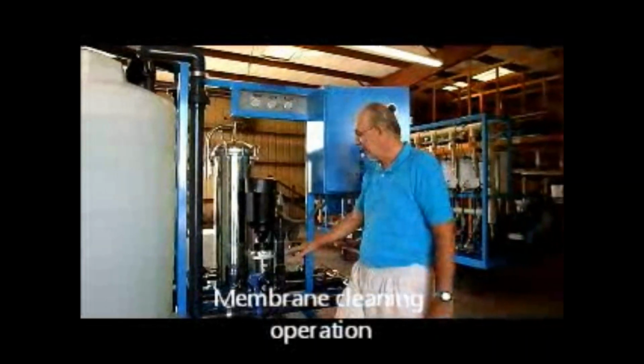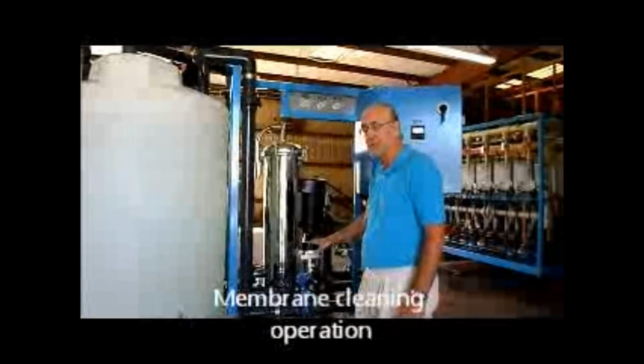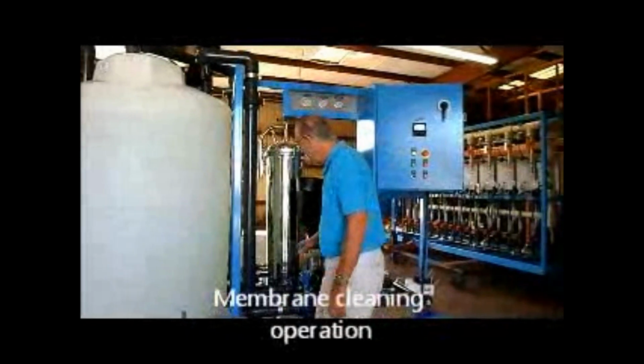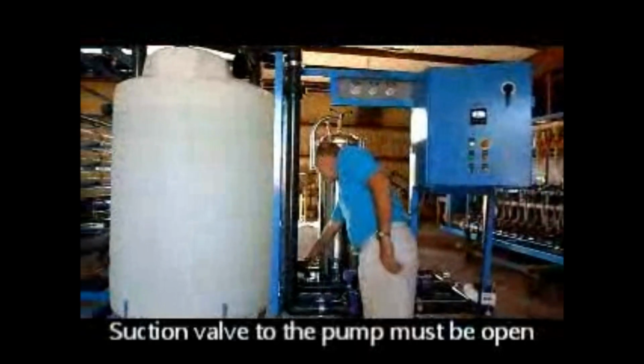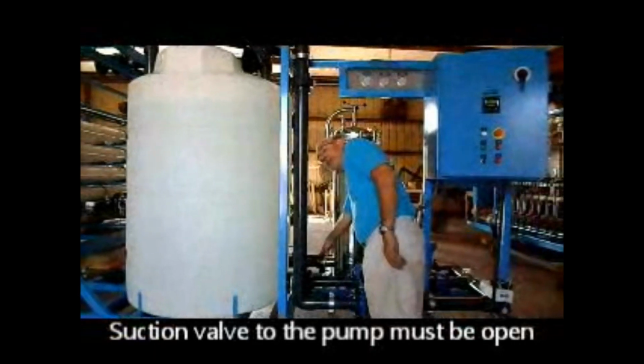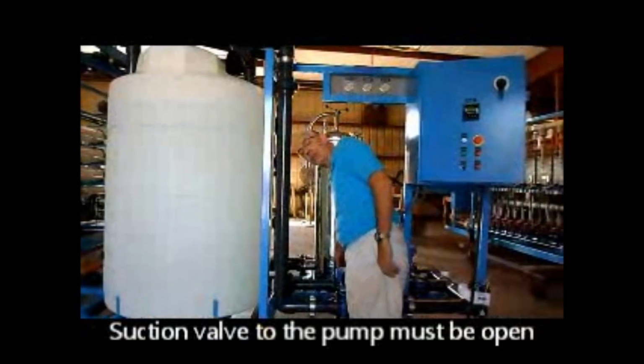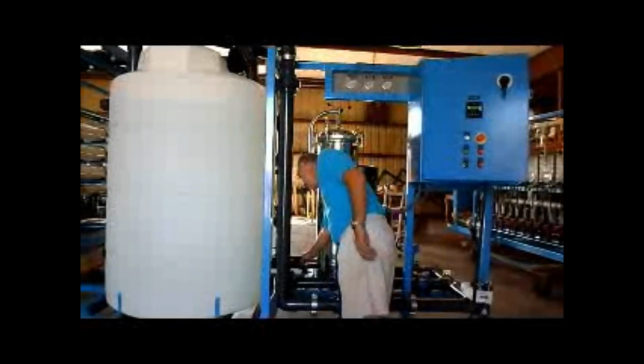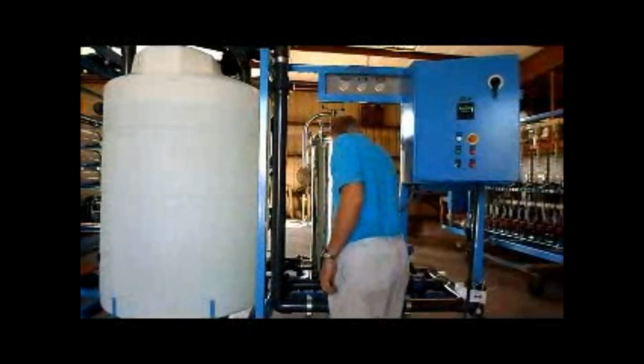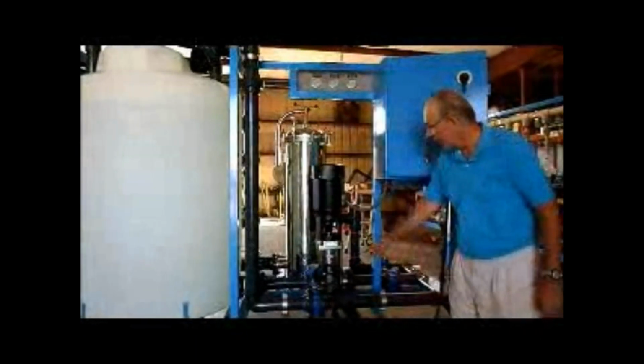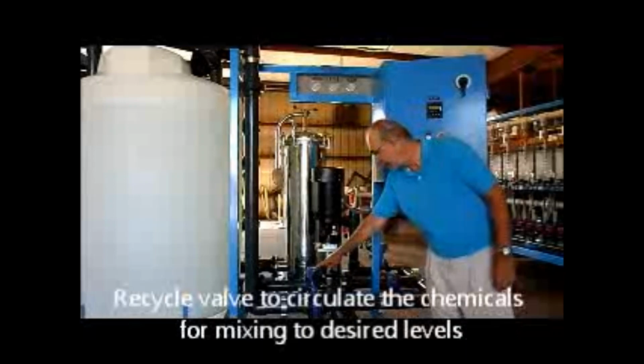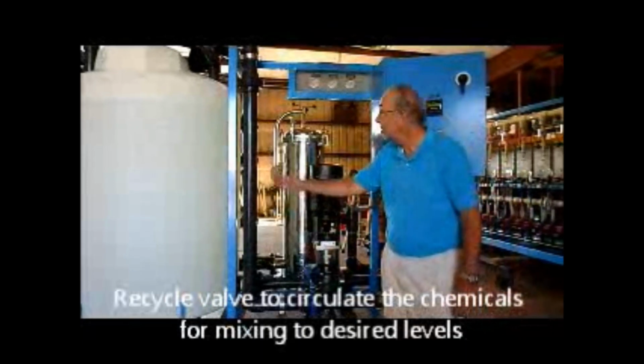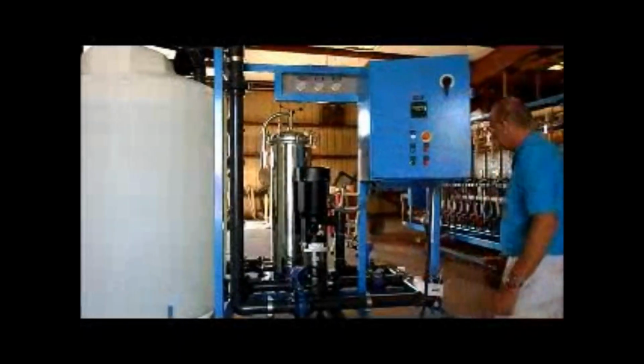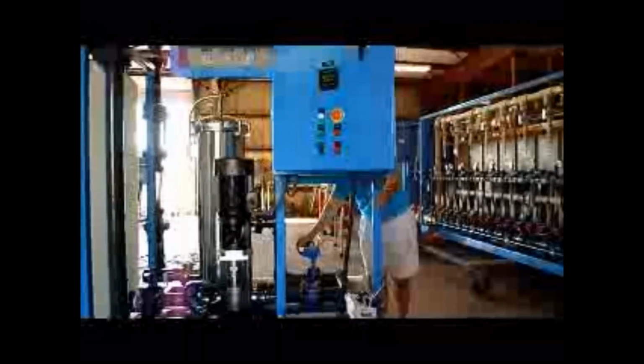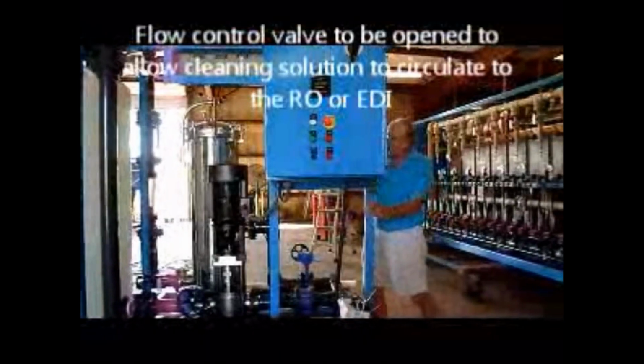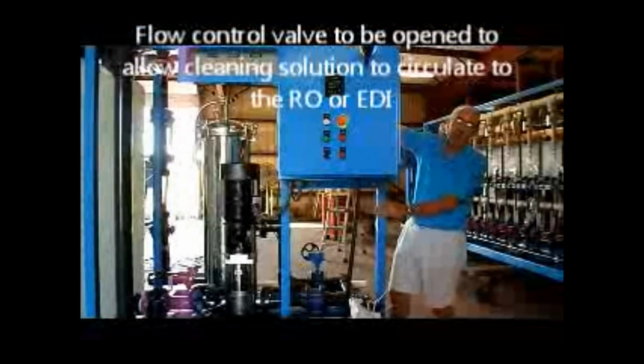Okay, now I'll explain how the system is operated using the valves that are installed on the system. First one, this is the suction valve into the pump. This valve's got to be open before the pump can run, otherwise the pump will not have any water coming in, it'll run dry. Keep this valve in open position. Then we have 2 adjustment valves. This one is what we call the recycle valve because it allows the cleaning solution to recycle back into the tank. This valve, flow control valve, allows the cleaning solution to go out through the cartridge filter and out to the RO or EDI skid.